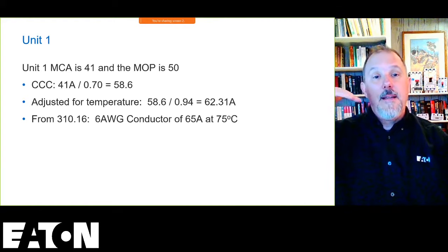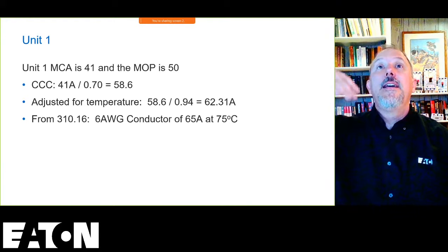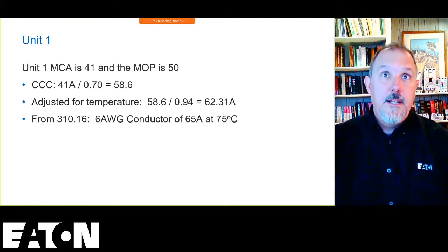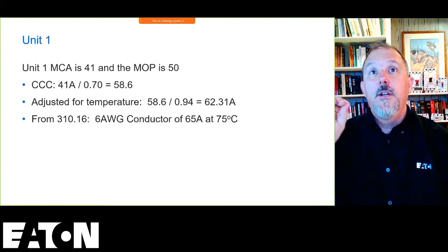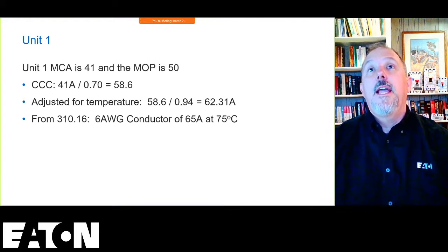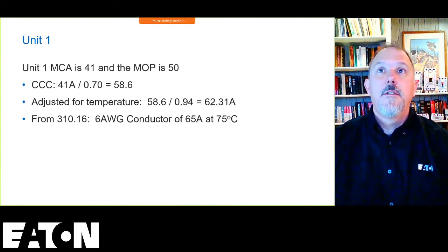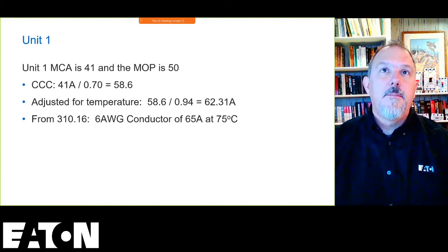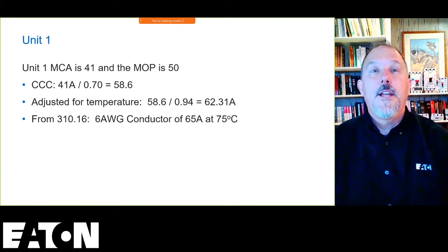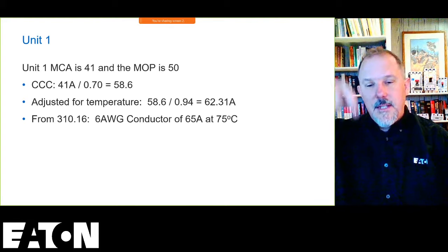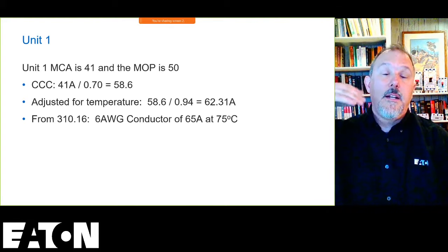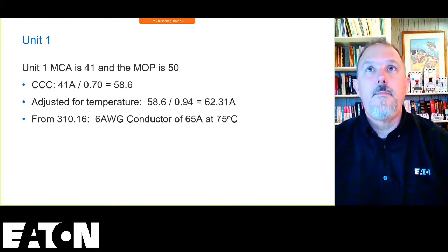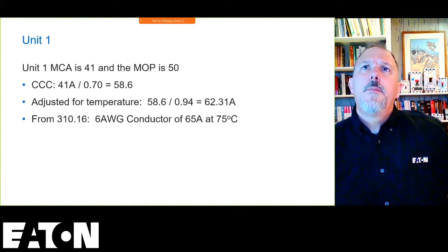I went through this, again, as an analysis to show how we calculate the equipment grounding conductor size. I think the engineer required one in each. But to your point, Joe, it depends on the raceway they're using, threaded conduits, all that good stuff. An EGC is required, but the metal conduit is an EGC. In this case you obviously need an equipment grounding conductor, but you're leveraging the metal raceway conduit. Excellent. Good feedback.